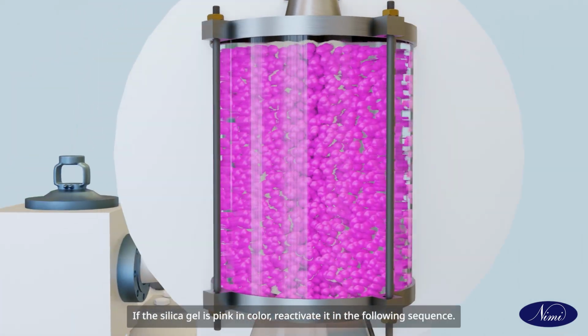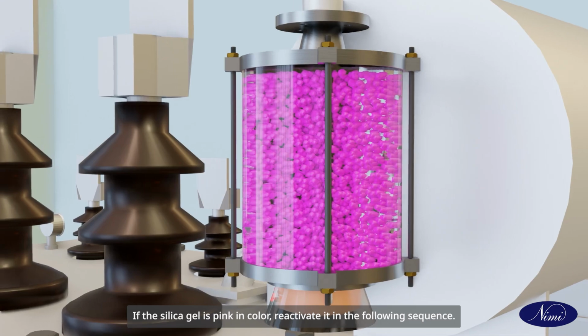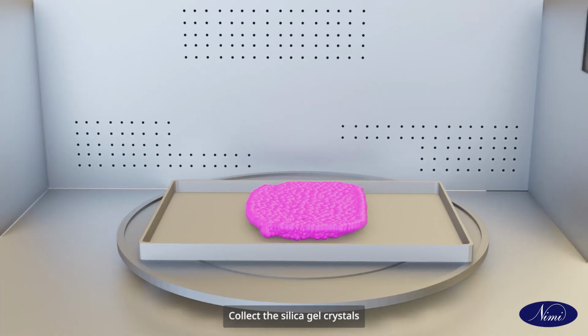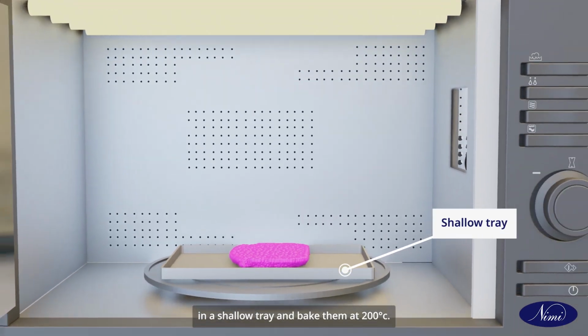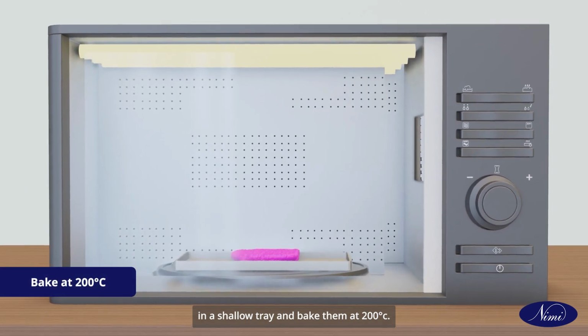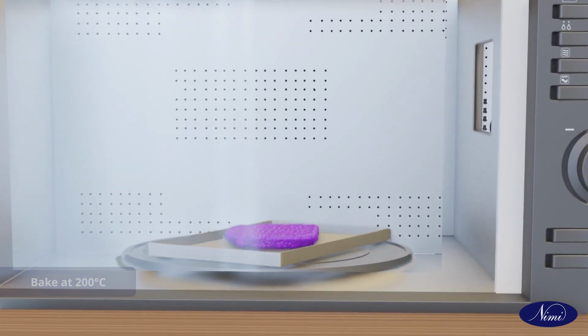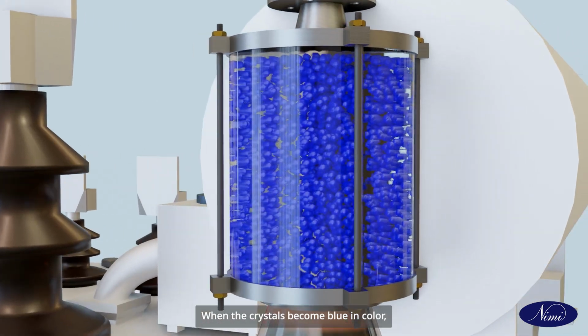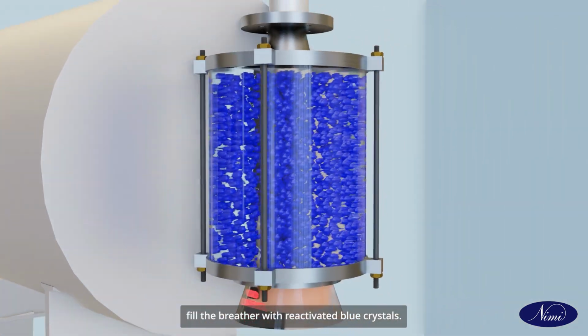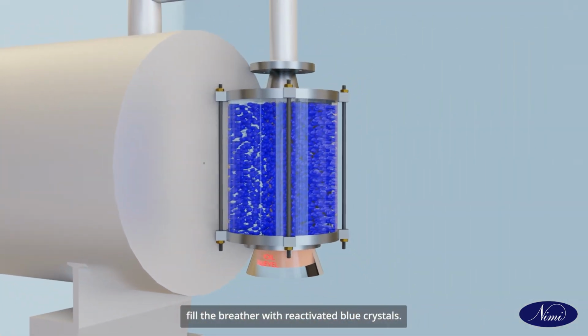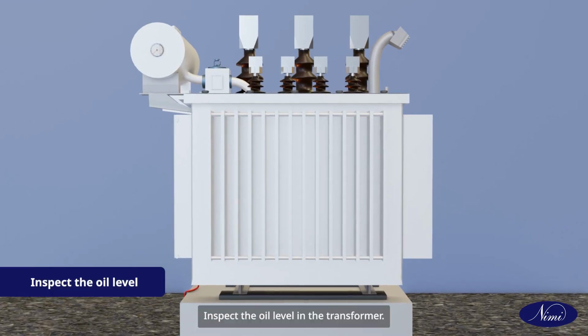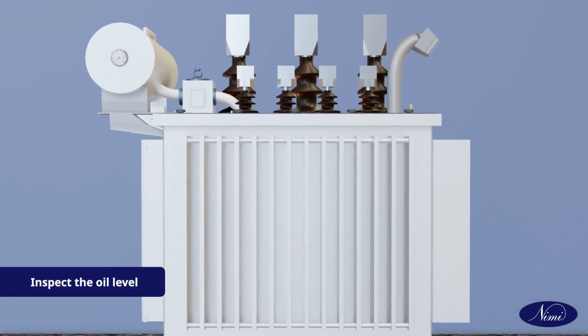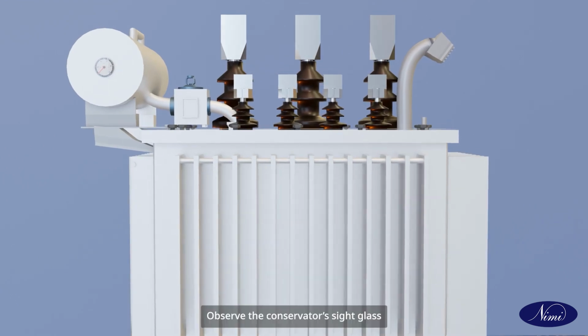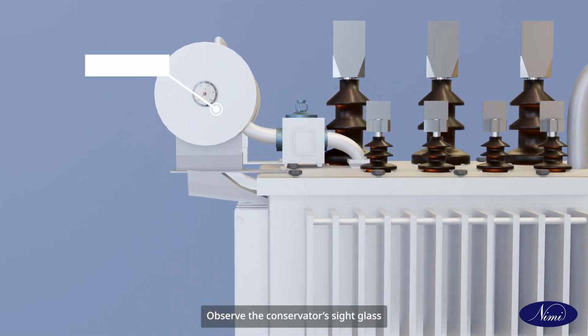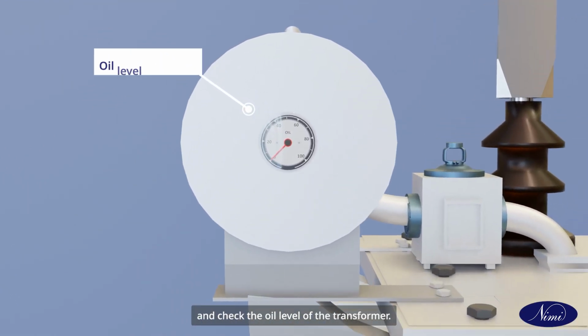If the silica gel is pink in color, reactivate it in the following sequence. Collect the silica gel crystals in a shallow tray and bake them at 200 degrees Celsius. When the crystals become blue in color, fill the breather with reactivated blue crystals. Inspect the oil level in the transformer. Observe the conservator's sight glass and check the oil level of the transformer.